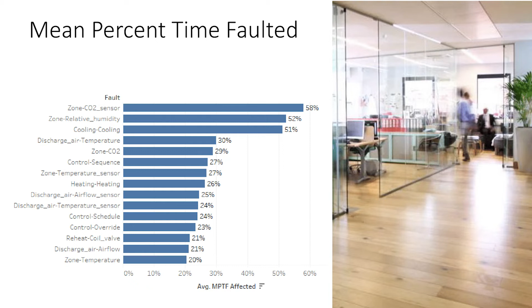Looking at the time dimension—the amount of time spent faulted—we have three areas that are pretty high: zone CO2 sensors, relative humidity, and cooling, which shows up twice because it's so good. This cooling fault might occur if the building is scheduled to be unoccupied with nothing running, but cool air is still flowing—we just call that a generic cooling fault, which can have many causes. So half the time or more spent with these faults reported is definitely an issue, and that's going to play a big part in your life if you're using these kinds of tools.